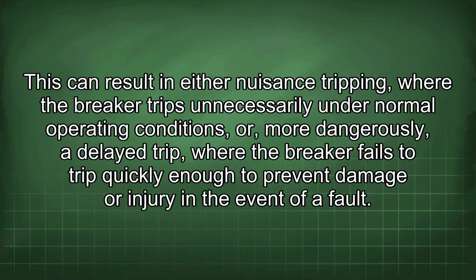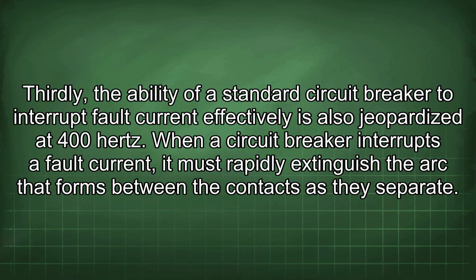This can result in either nuisance tripping, where the breaker trips unnecessarily under normal operating conditions, or, more dangerously, a delayed trip, where the breaker fails to trip quickly enough to prevent damage or injury in the event of a fault. Thirdly, the ability of a standard circuit breaker to interrupt fault current effectively is also jeopardized at 400 Hz.